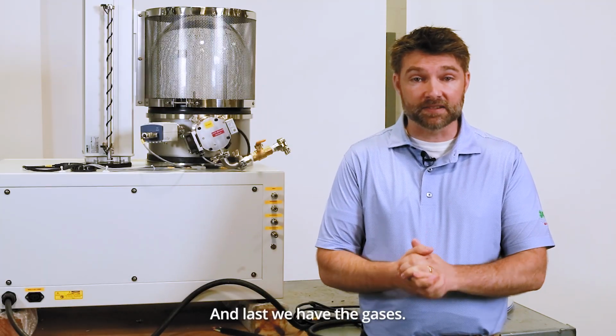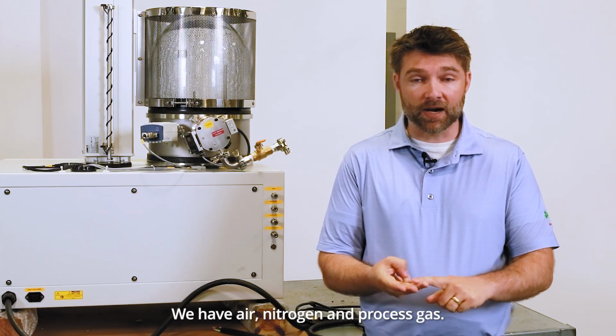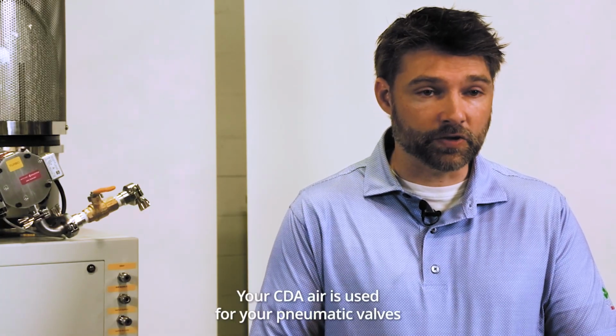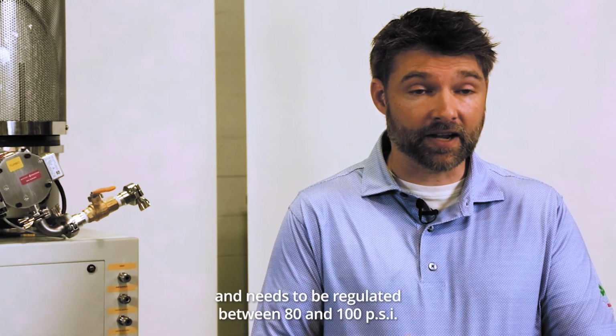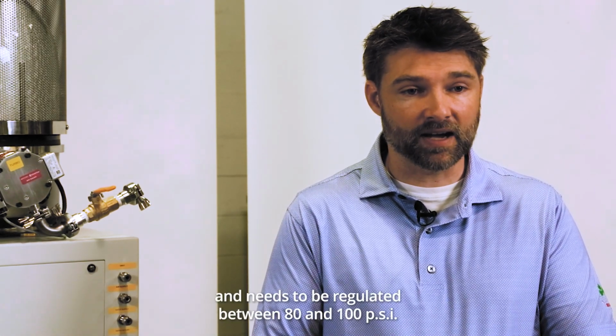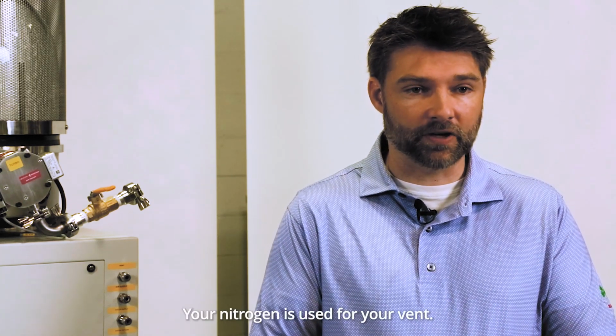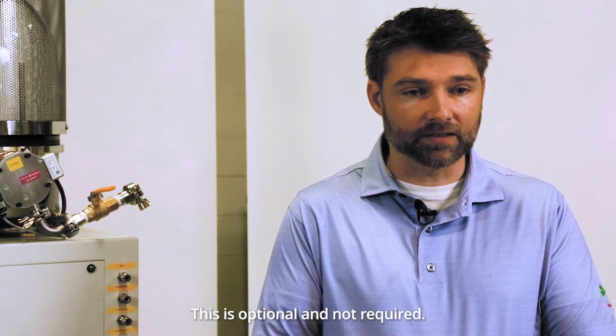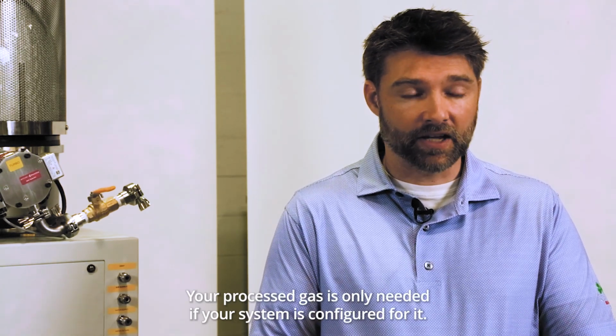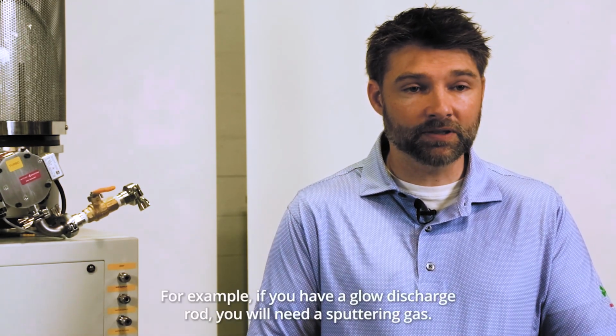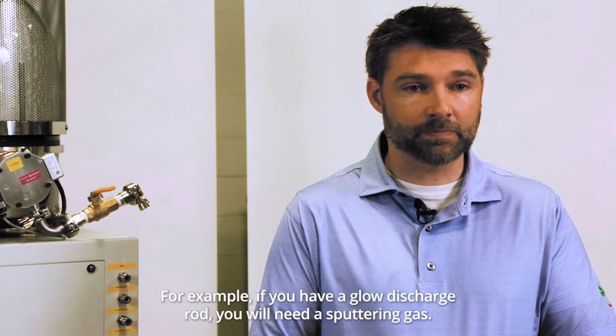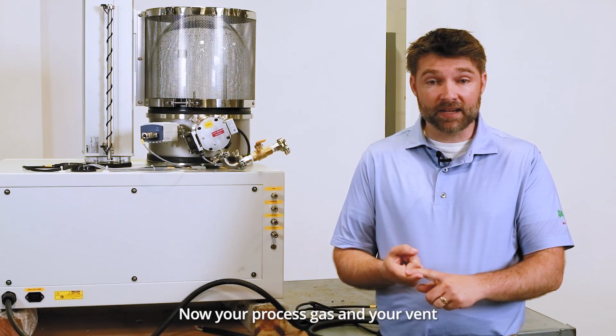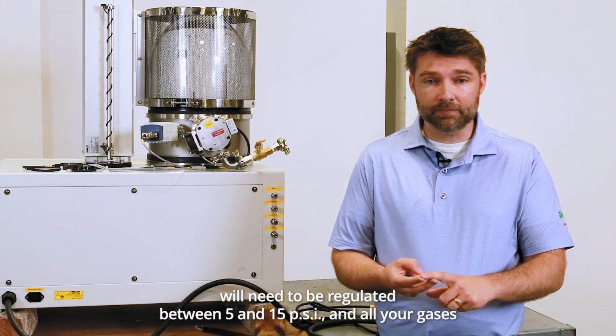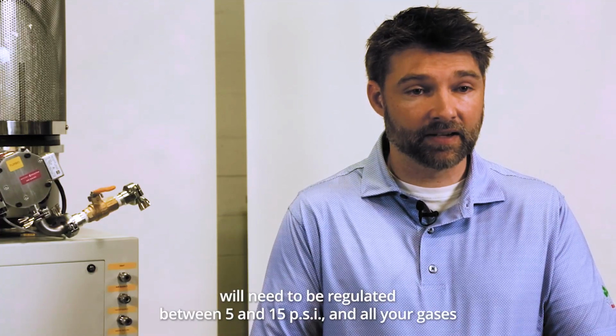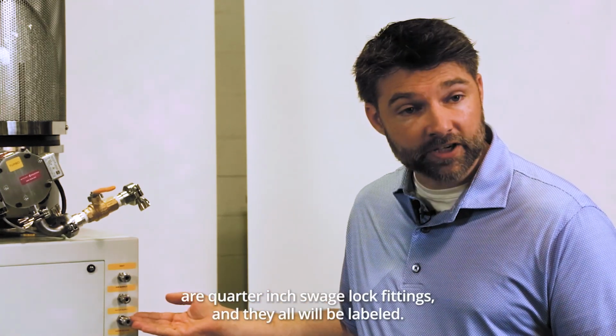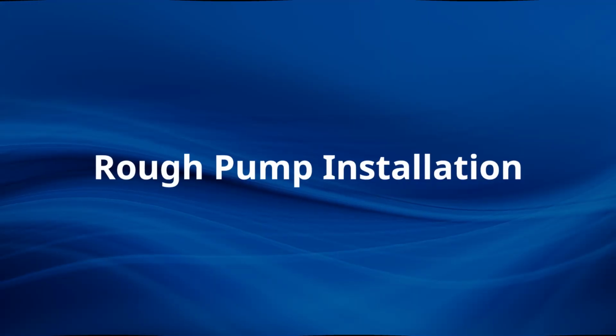And last, we have the gases. We have air, nitrogen, and process gas. Your CDA air is used for your pneumatic valves and needs to be regulated between 80 and 100 PSI. Your nitrogen is used for your vent. This is optional and not required. Your process gas is only needed if your system is configured for it. For example, if you have a glow discharge rod, you will need a sputtering gas. Now, your process gas and your vent will need to be regulated between 5 and 15 PSI. And all your gases are 1/4-inch Swagelok fittings, and they all will be labeled.